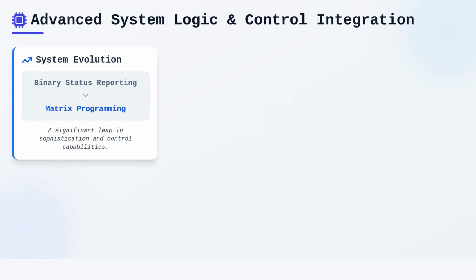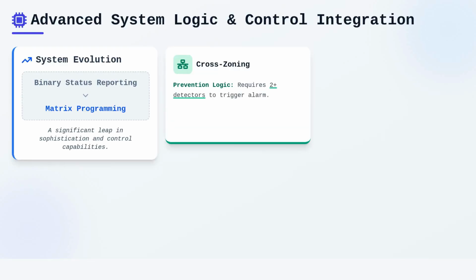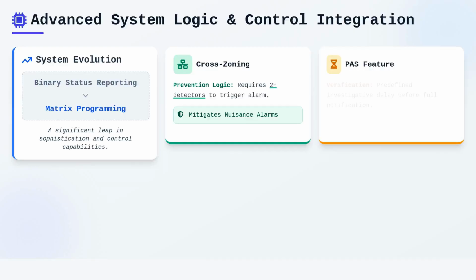When we examine the logic governing these units, the transition from simple binary status reporting to complex matrix programming represents a significant leap in system sophistication. Modern panels allow for cross-zoning, a logic sequence where the FACP only initiates a general alarm or suppression release once 2 or more separate detectors confirm an event, thereby mitigating the risk of inadvertent nuisance alarms. Furthermore, the positive alarm sequence feature introduces a predefined investigative delay, granting trained personnel a window of time to verify the incident before the building-wide notification sequence commences.